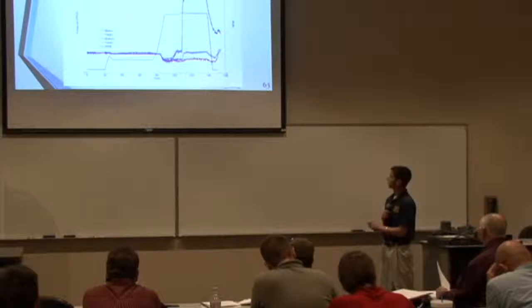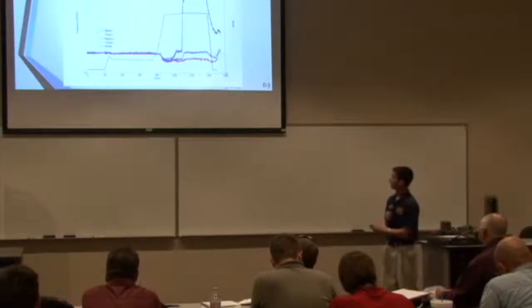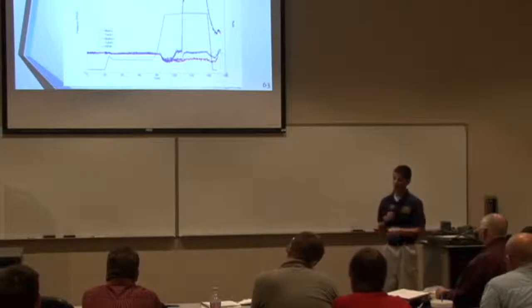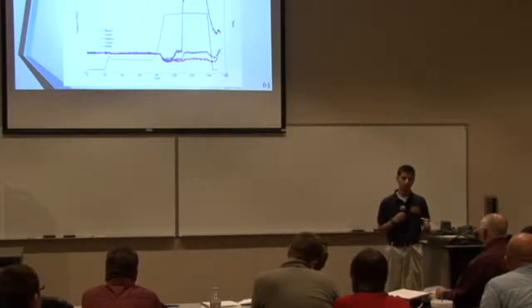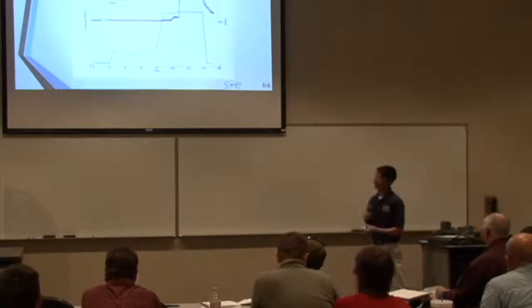So what we can see from that is the static pressures begin to climb back up to where they were originally before we started the test. Now, the difference here in these two static pressures is, we believe, due to the burrs that are still located inside the test sections, possibly causing the pressure to be different. So again, the same test.